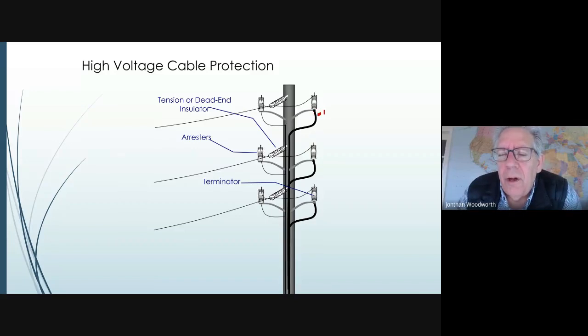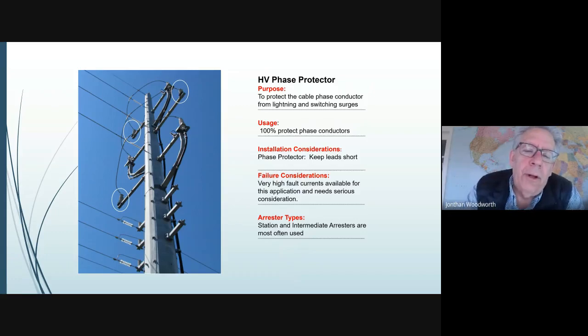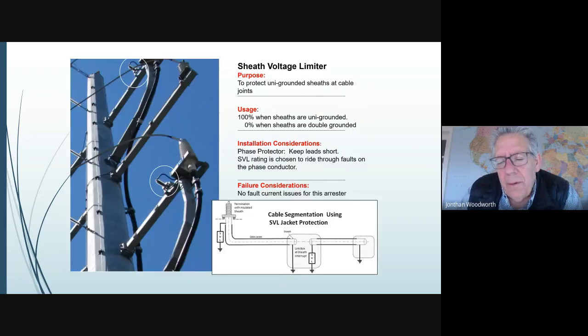And when I say high voltage, say 245 kV or 115 kV, this cable needs to be protected, both the sheath and the center conductor. This is an actual pole showing the arrestor is tied all the way over here to this phase conductor, and that's protecting the phase conductor. And then this is a sheath voltage limiter here that's actually protecting the sheath on this one. The sheath voltage limiter is a kind of an uncommon type of arrestor, but it's used in high voltage cable protection.